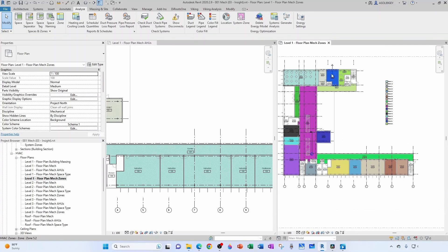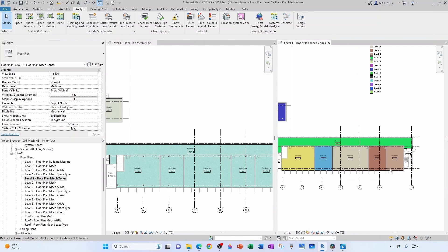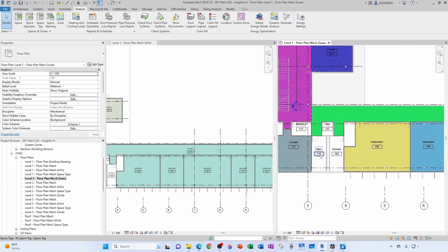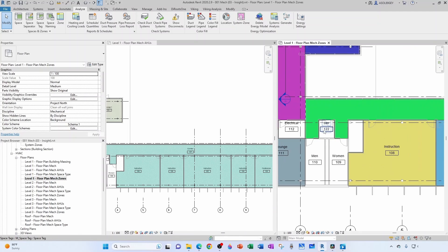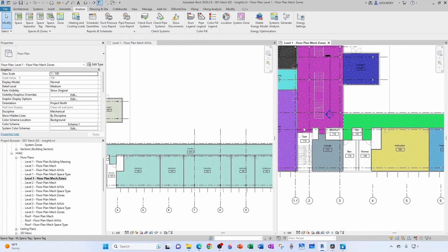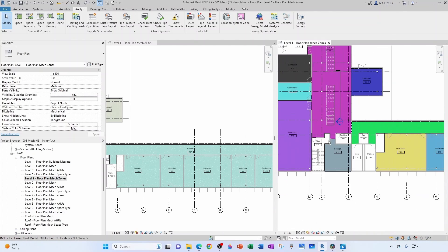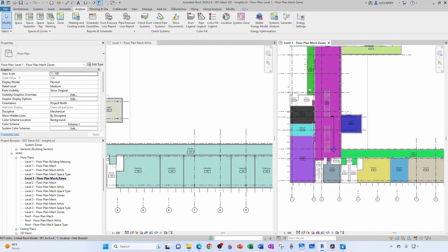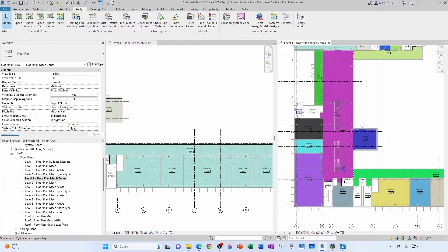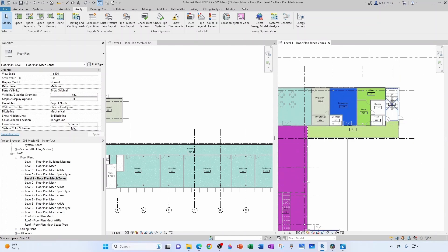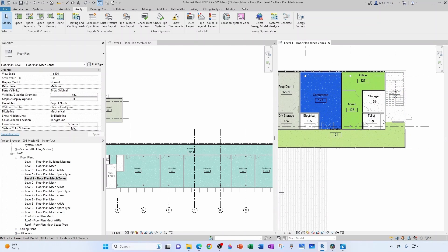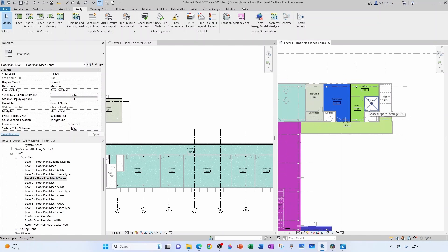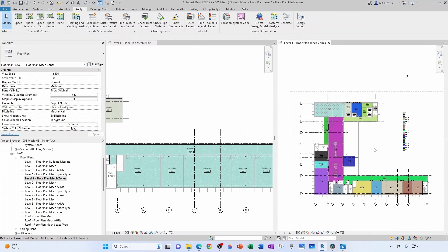So we have all our zones for level one. Just make sure we're not missing anything. Stairs are unconditioned, men and women and janitors are going to bring it in from the corridor with louver doors. Electrical is a different animal, this is a shaft, stairs unconditioned, electrical different animal, sprinkler a different animal, electrical different animal, toilet and storage are both going to be served by this area with louver door, and stairs unconditioned.